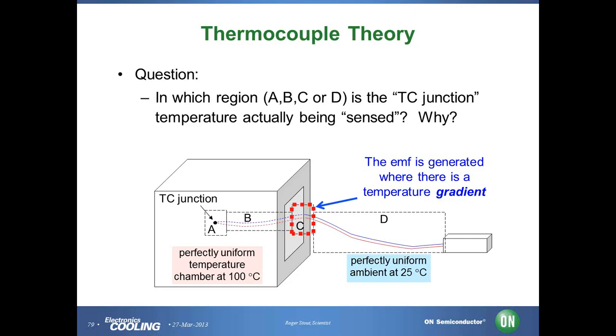interior to the outside. To truly calibrate this thermocouple, then sticking the junction into a known temperature bath doesn't do squat, if the gradient during the calibration procedure occurs 5 centimeters from the junction, but in my typical use the thermocouple gradient occurs anywhere from ½ a centimeter to 50 centimeters from the junction.